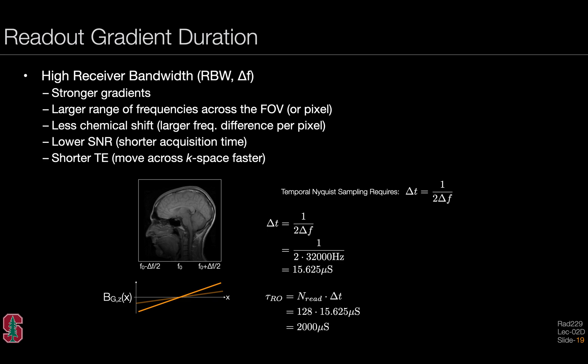In addition to calculating the readout amplitude, we would want to calculate the readout gradient duration. We know that the temporal Nyquist sampling requires that we have a delta T equal to one over twice the delta frequency. We can rearrange this expression. We have the receiver bandwidth shown here on the bottom and we can get the delta sampling step time, which is about 15 microseconds in this case. If we want to sample in 15 microsecond steps for every readout point, we might be sampling 128 readout points for 128 pixel image. Multiplying that by the delta time step for each measured point gives us a readout duration of about 2000 microseconds.